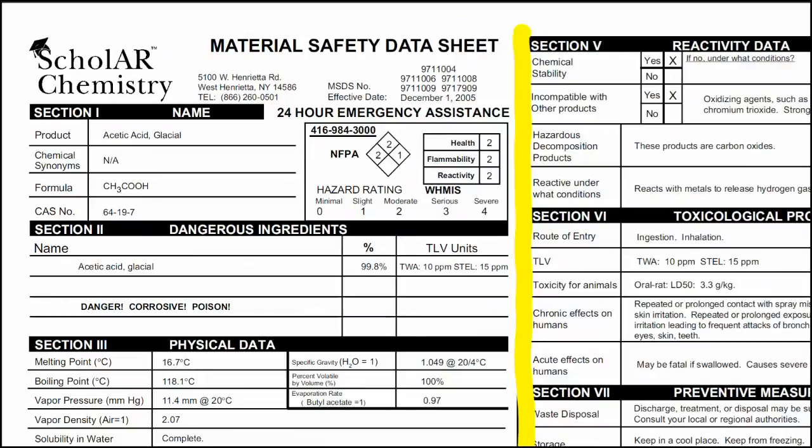Beside the product information, you can see the hazard ratings. There are typically two ratings on the MSDS: the NFPA rating for firefighters, and the WHMIS rating, which is our interest here. In the WHMIS rating there are three categories — health, flammability, and reactivity — with a number associated with the degree of severity of risk. The legend for these ratings is located right under the two charts.